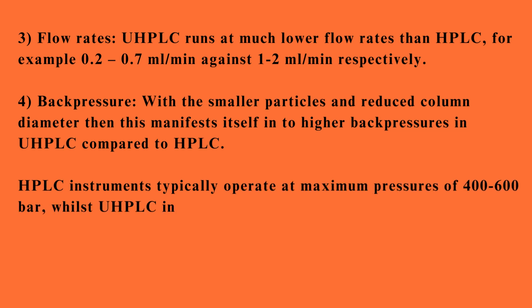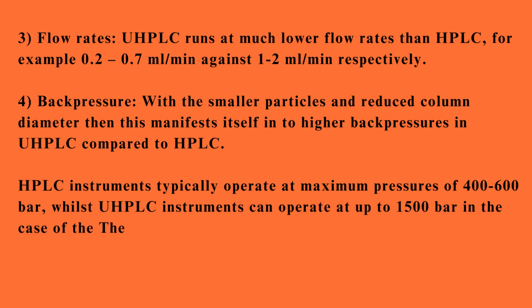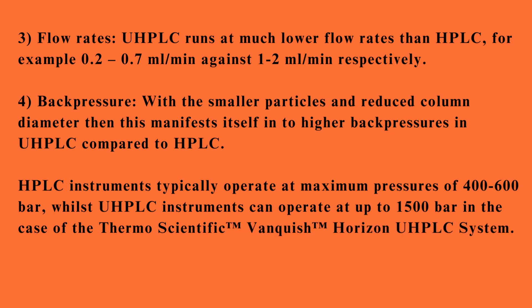HPLC instruments typically operate at maximum pressures of 400 to 600 bar, whilst UHPLC instruments can operate at up to 1500 bar, in the case of the Thermo Scientific Vanquish Horizon UHPLC system.